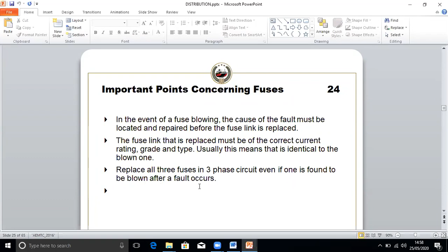In the event of a fuse blowing, the cause of the fault must be located and repaired before the fuse is replaced. The replacement fuse must be of the same current rating. Current should be the same, voltage should be the same. And replace all 3 fuses in a 3-phase circuit, even if only one is found to be blown after a fault current.